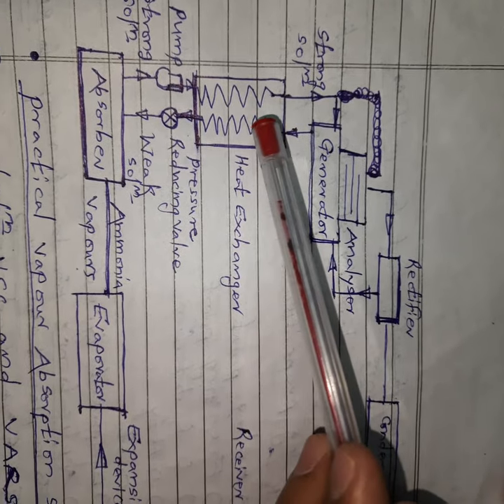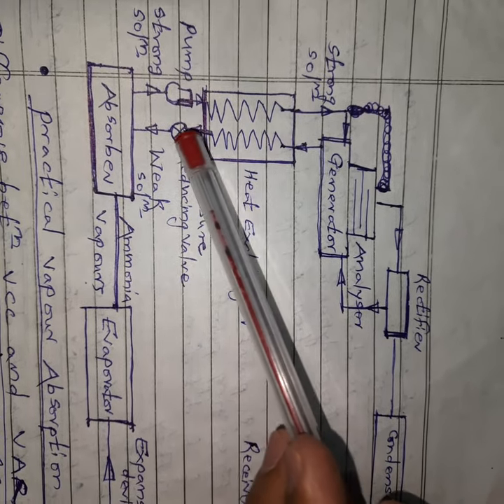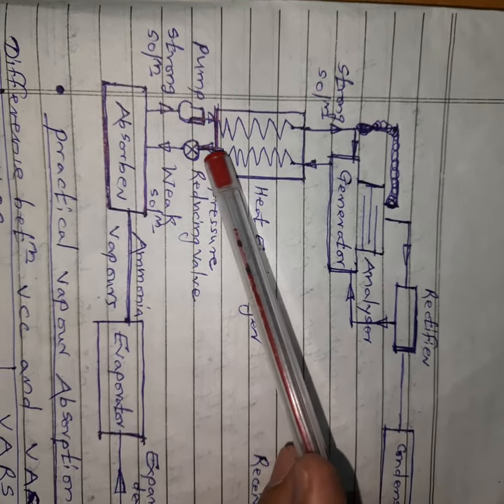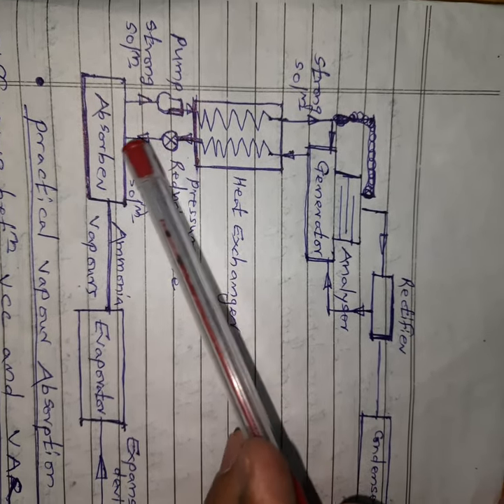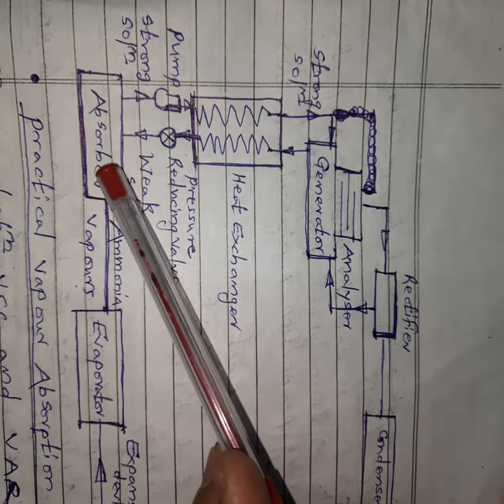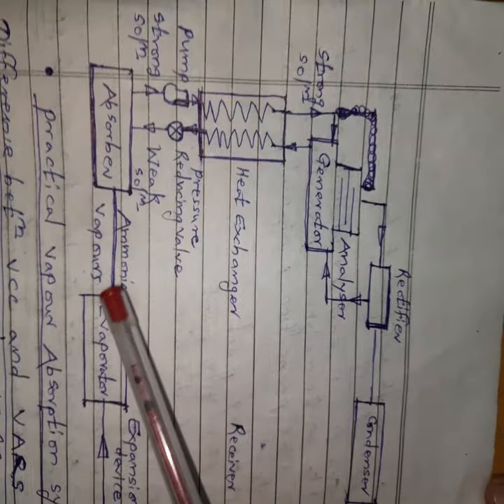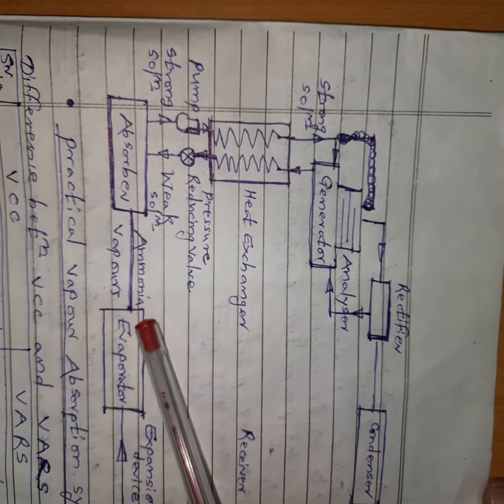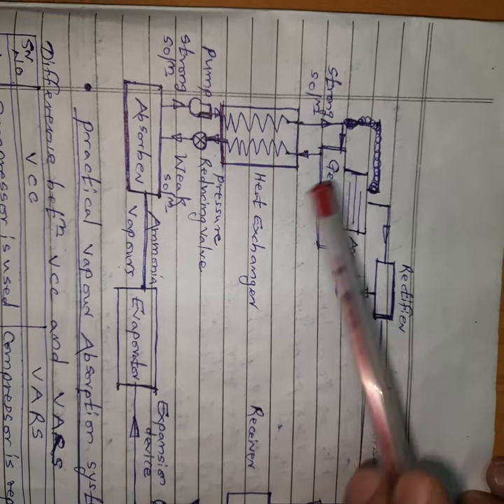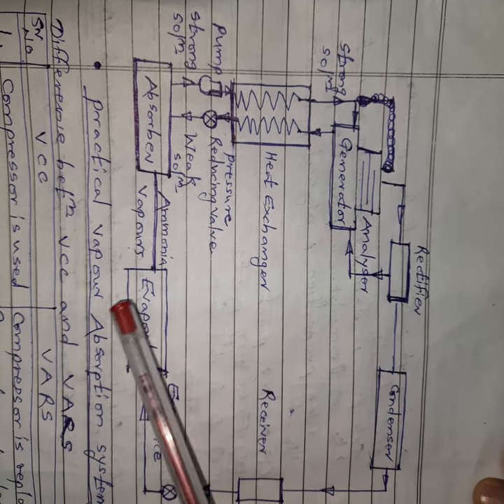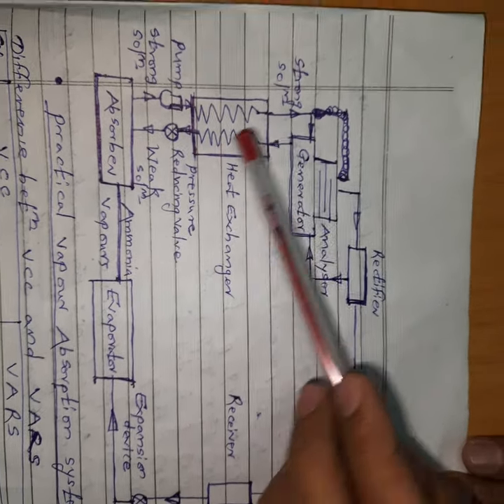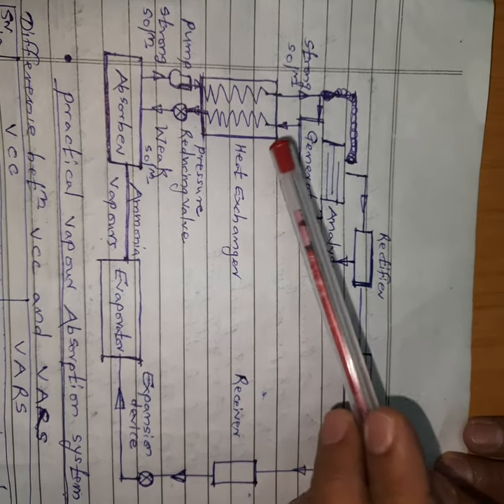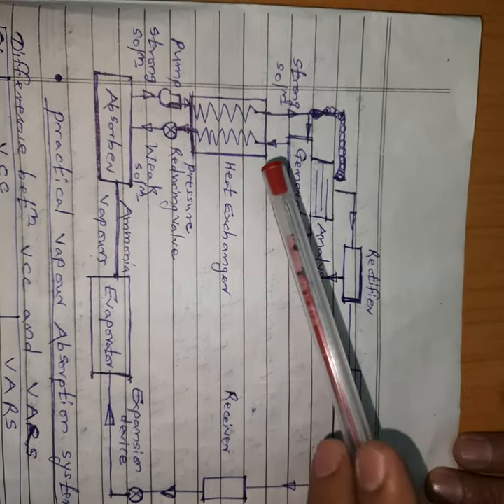When the cooled weak solution passes through the pressure-reducing valve, pressure decreases and temperature decreases. When this cold weak solution enters the absorber it can absorb more ammonia vapors, increasing output. Output increases, input decreases, and the overall coefficient of performance increases because of the heat exchanger. By simply using a heat exchanger, we can improve the COP of the vapor absorption system.